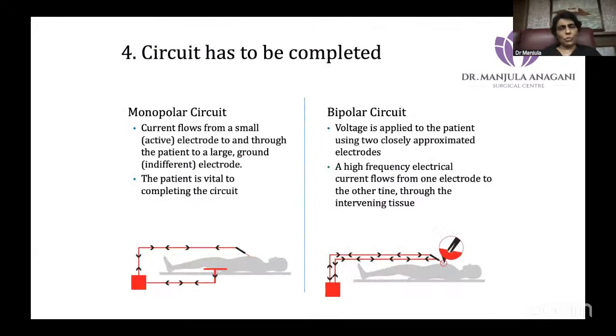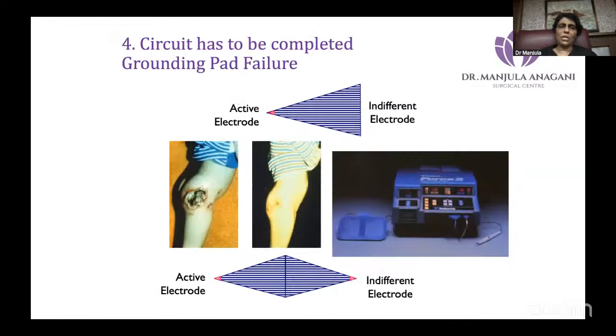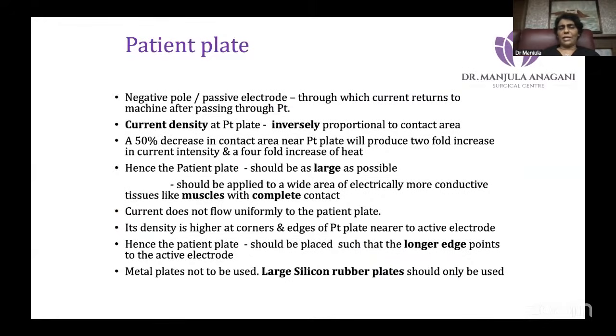Next, the circuit has to be completed. In monopolar, the patient is a part of the circuit. In bipolar, the patient is not a part of the circuit and the tip is a part of the circuit. To complete it, we have a grounding pad. We don't want this sort of energy. This is the active electrode and passive electrode, which we taught. Now, the patient plate is very important, which is the negative or passive pole. Current density is inversely proportionate to the contact area. So a smaller patient plate means more current will be concentrated there, so more damage. You need to use a patient plate which is as large as possible.